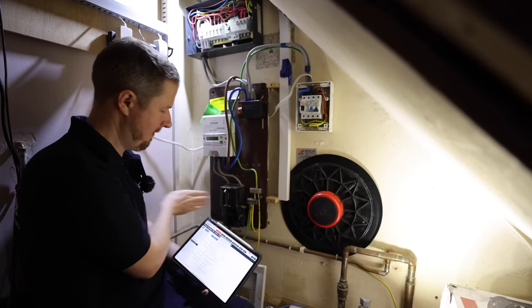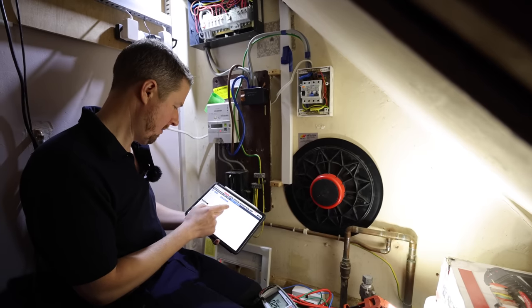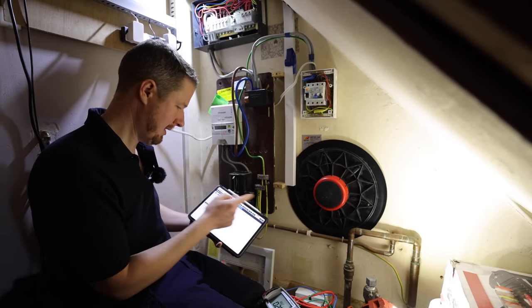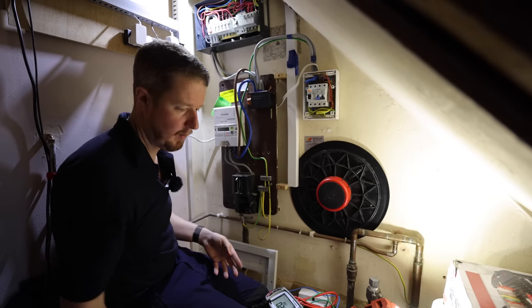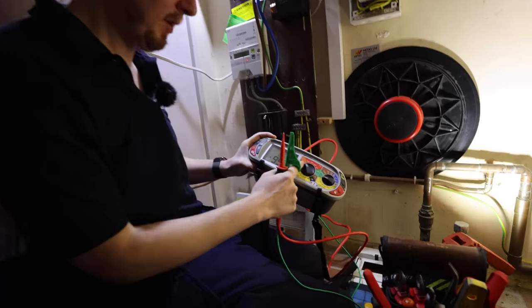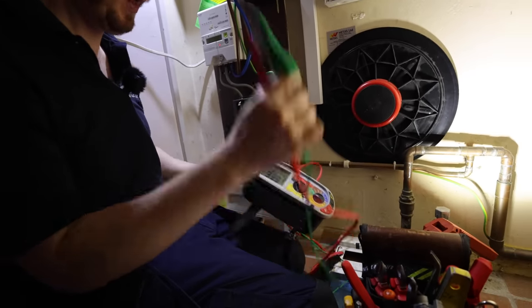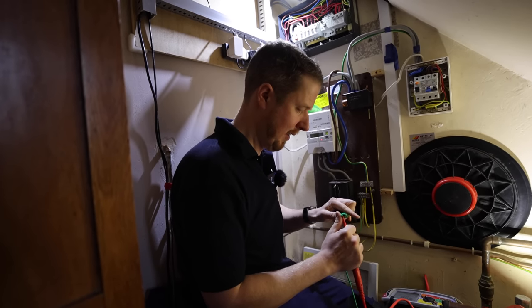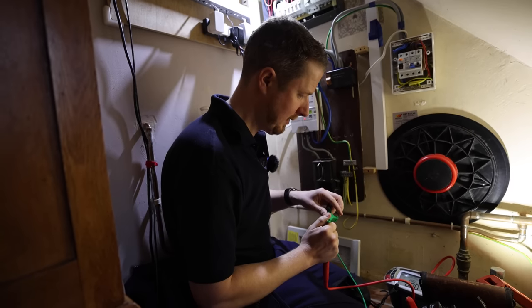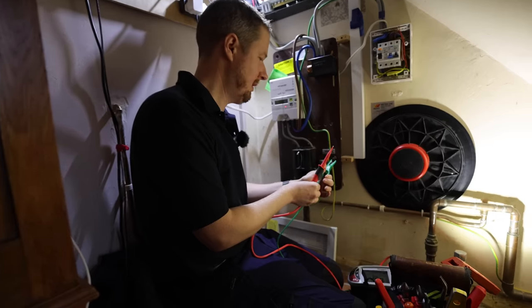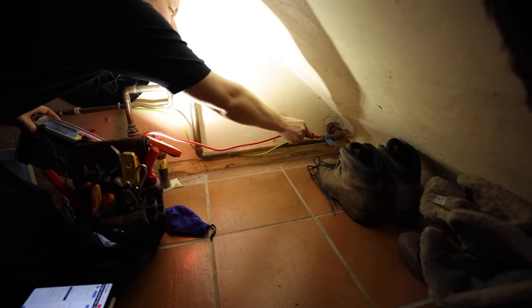Primary overcurrent device, now that is this. There's no way of identifying it without breaking the seals, so we don't actually know what it is, but these tails need upgrading by the DNO anyway. The main tails are actually okay, so what we'll do is recommend to the customer that they get the DNO out to upgrade these tails and to change the main fuse to 100 amp if possible. We'll put yes on continuity check for the moment, but we'll have to go through and actually do some tests on that. So we get our long wander lead now and we'll do our bonding tests. We're going to put it on the low resistance ohm setting, and then what we have to do is null the leads out, so we test these together.